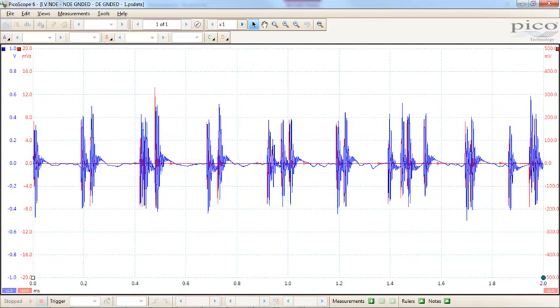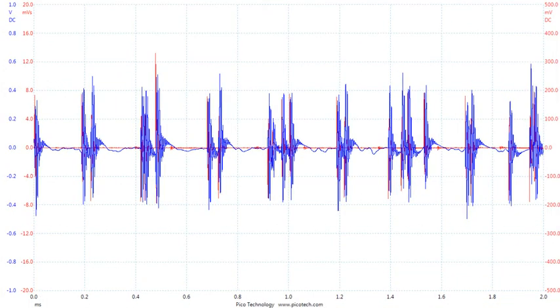So with the one way, you're actually measuring the circulating current. When we measured this, for instance, with both brushes grounded, you're actually looking at the circulating current. The way we managed to measure the circulating current was by comparing that current with the current of only one brush grounded.